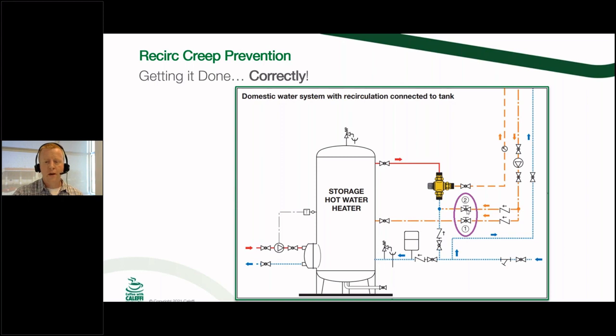So for this valve going back to the cold inlet, you'll notice too that there's a check valve right upstream on the cold side, so that this line has to go through the cold inlet of the mixing valve. It cannot go backwards through the tank to the hot inlet. And with this valve number 2, you're going to leave it completely wide open. And then valve number 1, you're going to open up just enough to maintain or add enough heat to the loop to maintain the temperature of that loop. So there's no specific flow rate that you're going to be looking for.